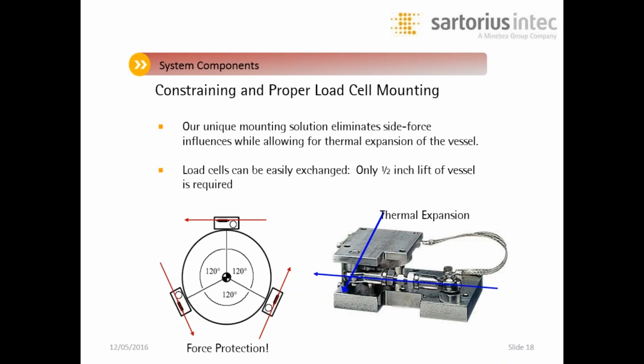Key to the sensitivity of quality load cells is side forces, and the built-in constrainer system. These constrainers, sometimes called check links, let me do this right here, keep the tank from twisting exactly where the force is most critical, directly at the load bearing point of the load cell. While external tank constrainers can serve the same purpose, they may hold the top of the tank while the bottom continues to move. It's always best to restrict tank movement where it counts the most, at the point of weight determination.